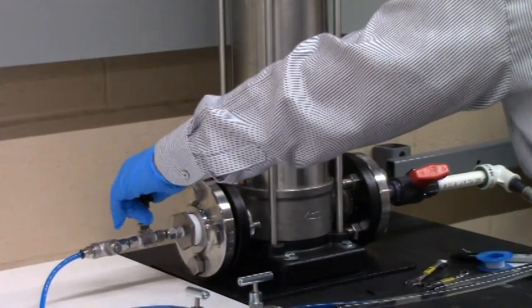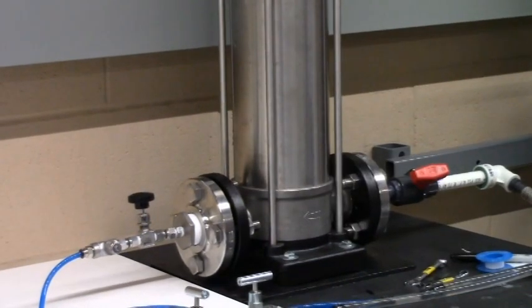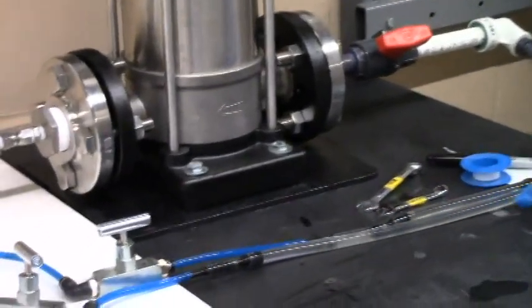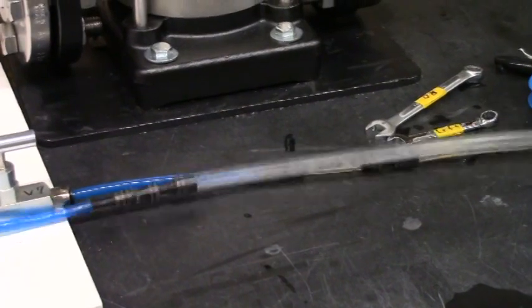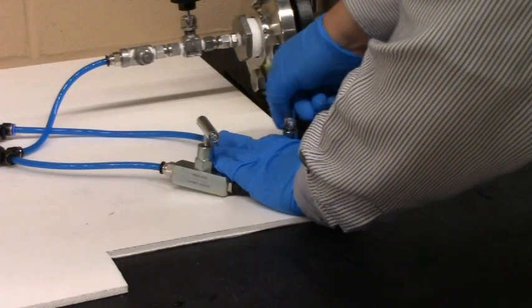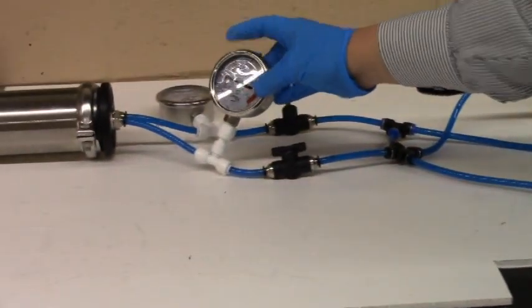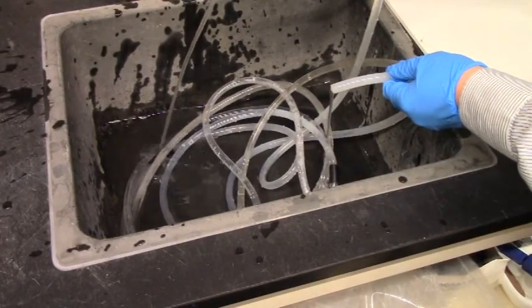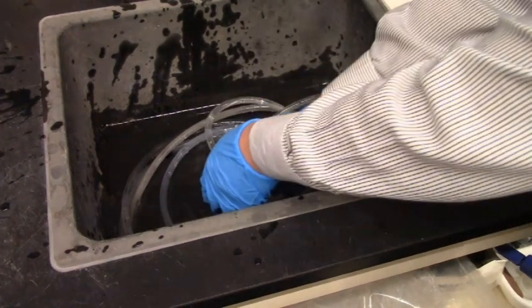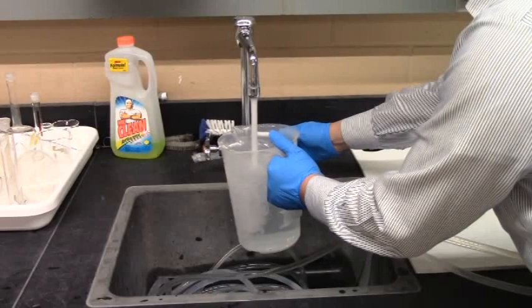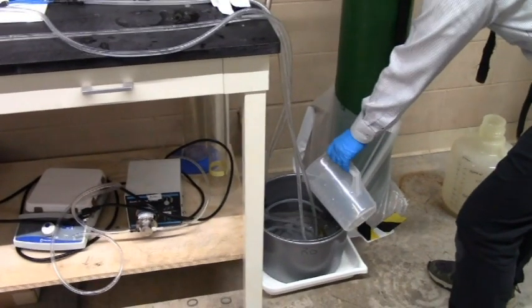Make sure water is flowing in the bypass lines. After a while, close the bypass valves one at a time and make sure the filter inlet pressure at gauge 1 increases. When the bypass valves are closed, more water will flow out of the filtrate line tube and reject line tube in the sink. Keep the water level in the bucket above halfway by continuously filling, transporting, and pouring water in the plastic jar. Use two plastic jars to fill and pour alternately.